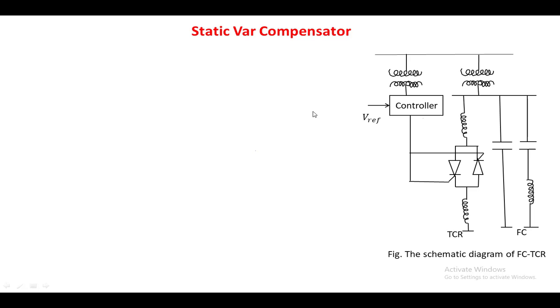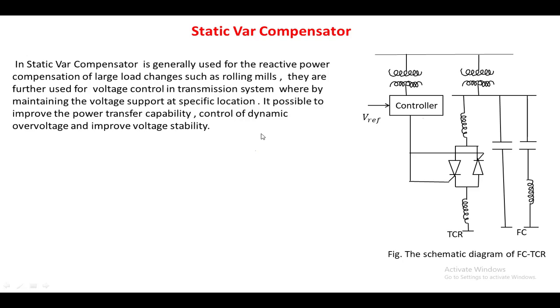The static VAR compensator obtains the required reactive power for the HVDC system by means of power electronic devices, which is why it is called a static VAR compensator. In the layout, there is a point where reactive power is applied, a controller for the TCR, a fixed capacitor, and a fixed capacitor along with a reactance. The controller provides gate pulses to thyristors T1 and T2.